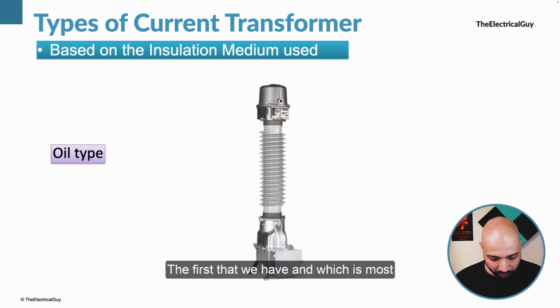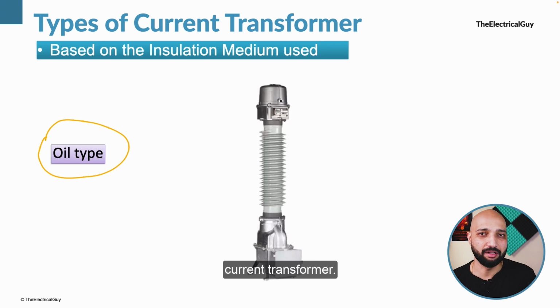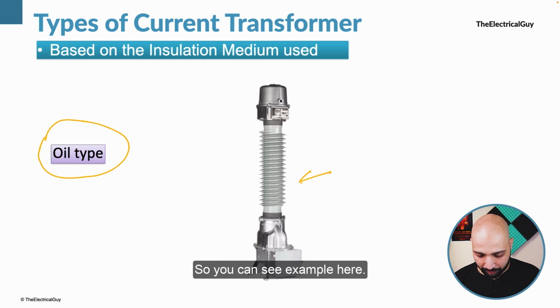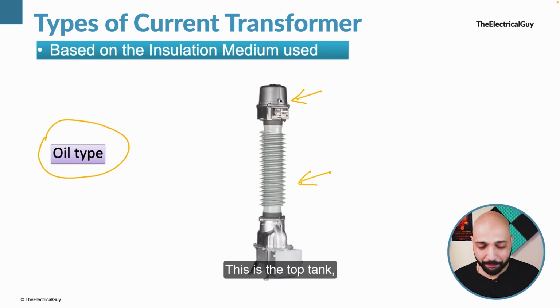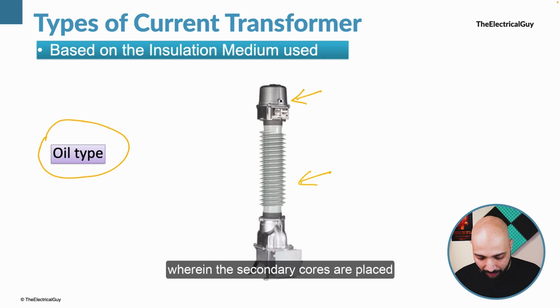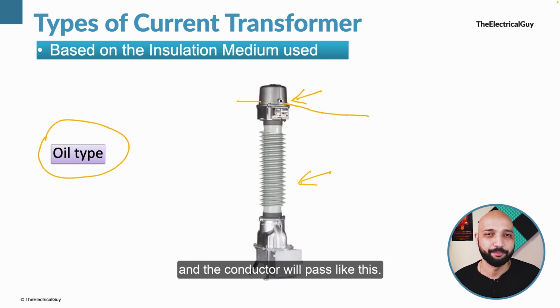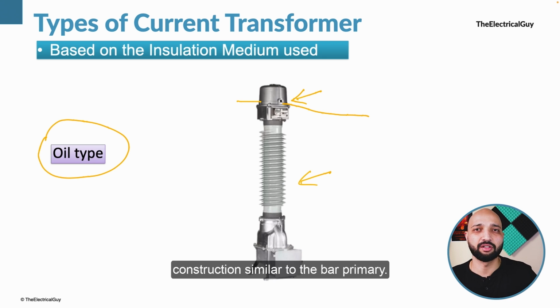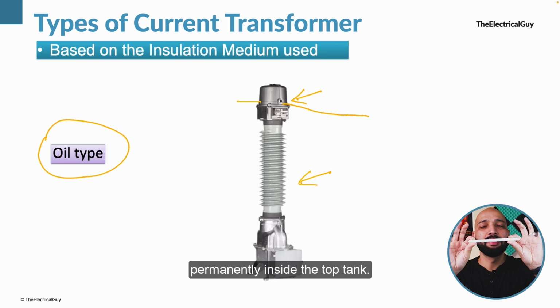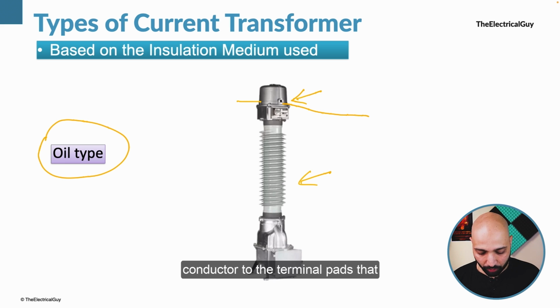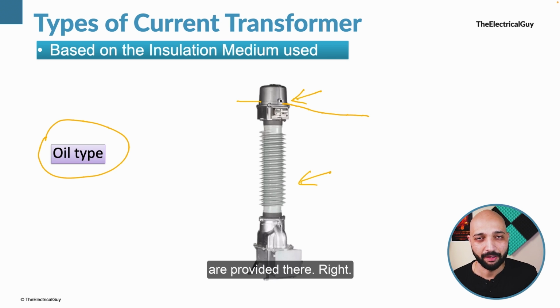The first that we have, and which is most commonly used, is the oil type current transformer. So you can see an example here. This is the example of a high voltage current transformer. This is the top tank wherein the secondary cores are placed and the conductor will pass like this. So basically you can relate the construction to the bar primary. So there will be a bar placed permanently inside the top tank. And you just have to connect the conductor to the terminal pads that are provided there, right? But in this tank, there will be oil filled for insulating purpose.